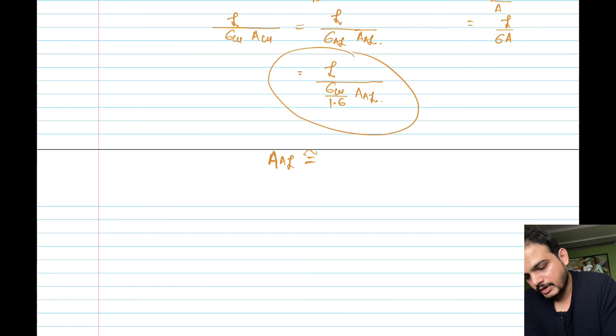So from this formula, we can write for copper: length of copper divided by sigma of copper into area of copper, which is equal to length of aluminium divided by sigma of aluminium into area of aluminium. Now in place of sigma aluminium, from this relation we can write length upon sigma copper divided by 1.6, into area of aluminium. After rearranging all these terms, the area of cross section for aluminium, for the same operating voltages, will be approximately equal to 1.6 times the area of copper.